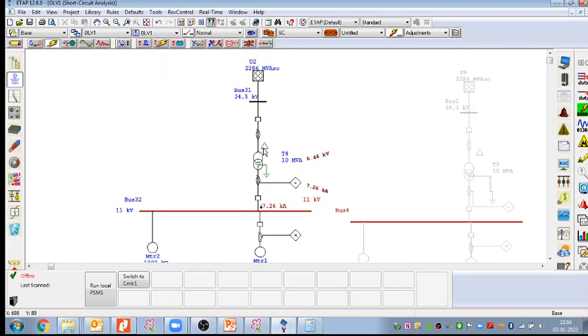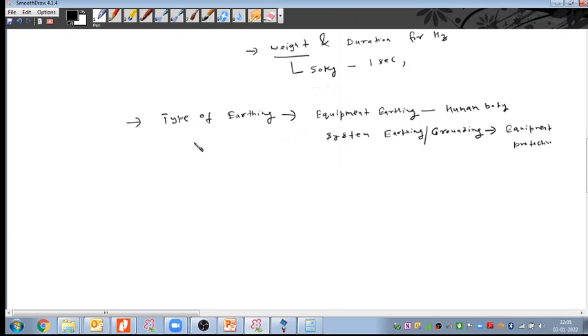So with the help of the grounding, we can see that this current we can now sense. So all the earthing, all the grounding that we do for the neutral, is only to sense the ground fault current, not the three phase fault current. I hope this statement is clear to everyone. If clear, then please let me know.